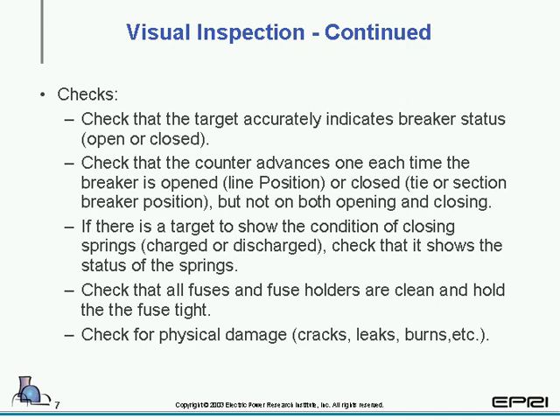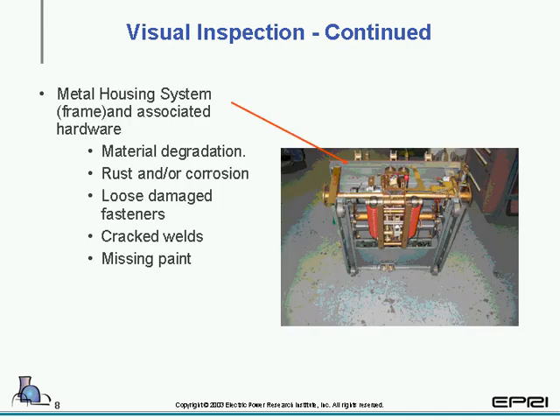And to continue on, we're going to check for the target accuracy. We're going to check the counters. We're going to show that the condition of the opening and the closing springs. We're going to check that all fuses and fuse holders are clean and there's no physical damage. That was a general overview of everything that you're going to want to look at as we continue looking at the individual or subcomponents of the breaker now.